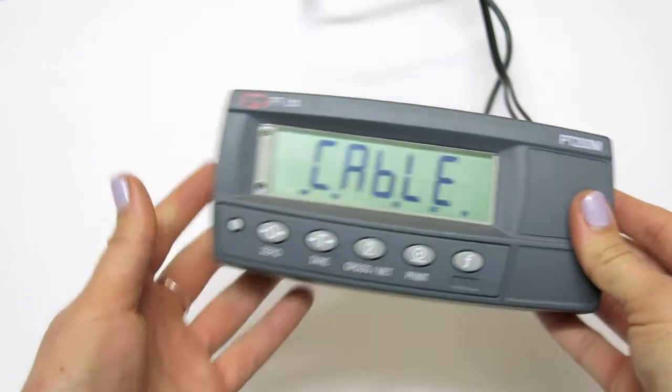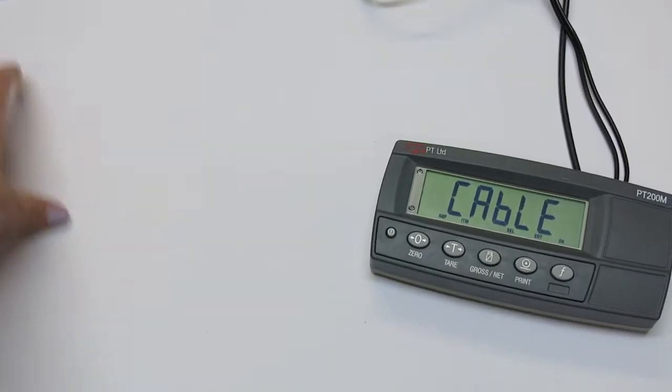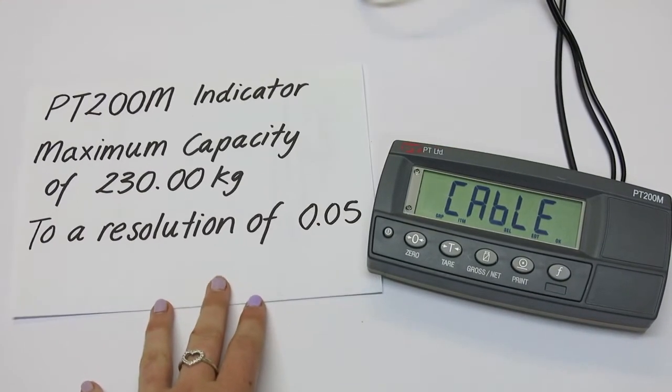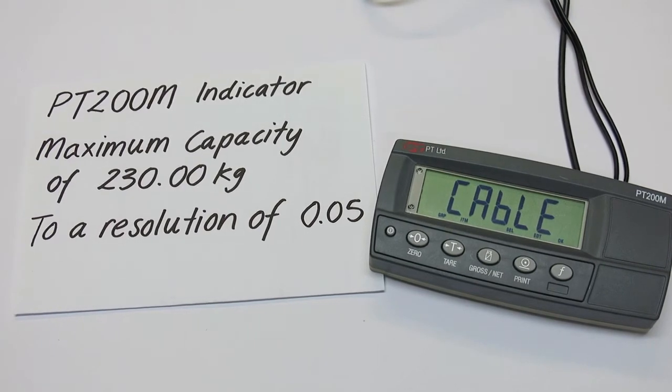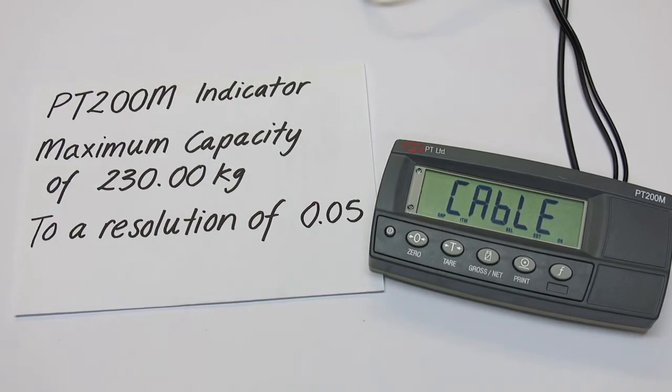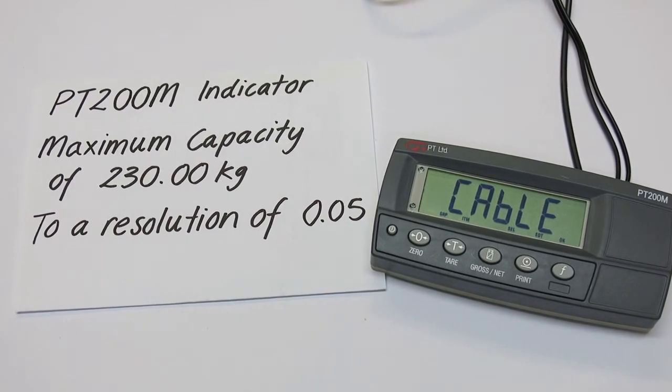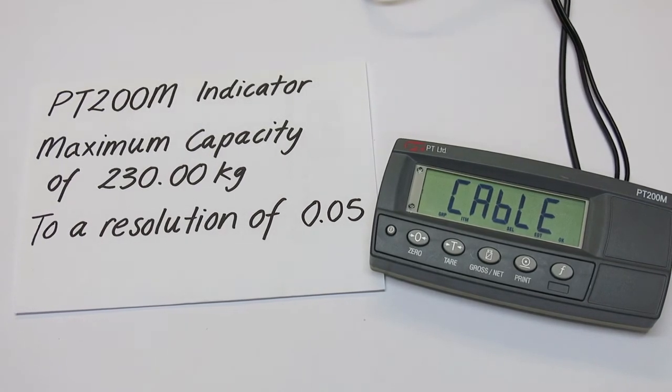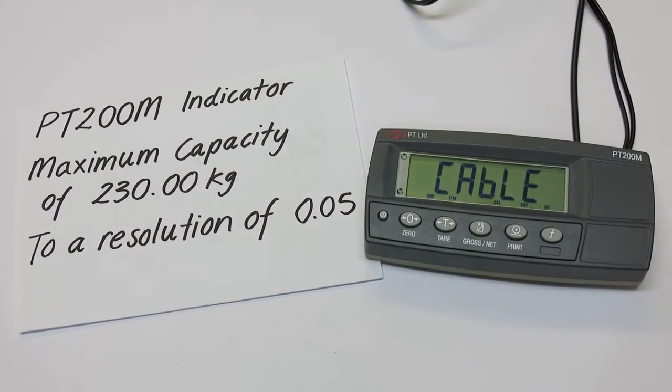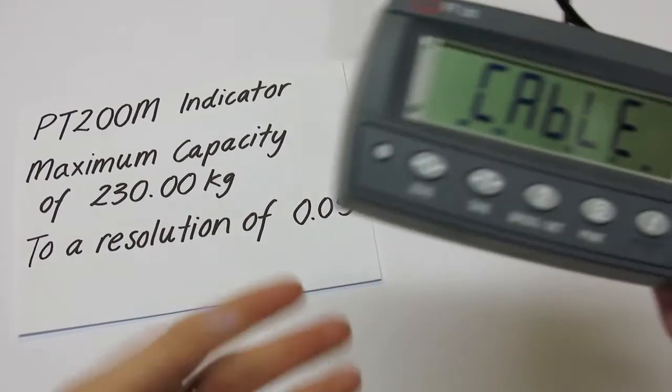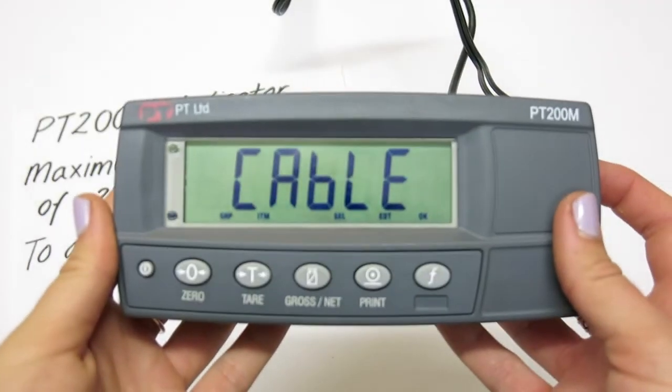For example, if we wanted the indicator to meet a certain set of requirements such as these, we would need to work through the build menu and define each parameter to get us a maximum capacity of 230 kgs to 2 decimal places with a resolution of 0.05. The first parameter we set is the decimal place depending on the amount of resolution needed.